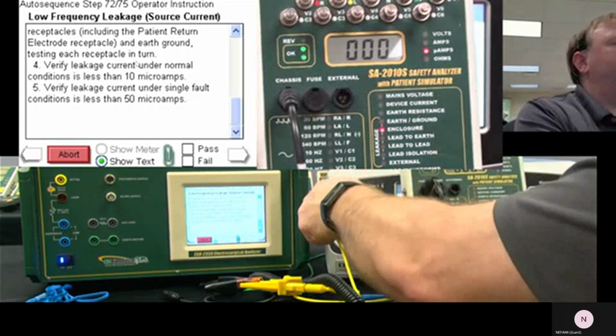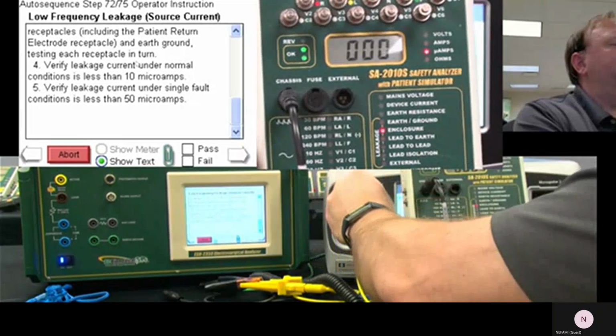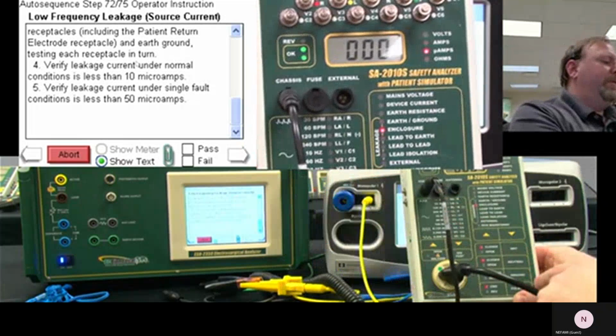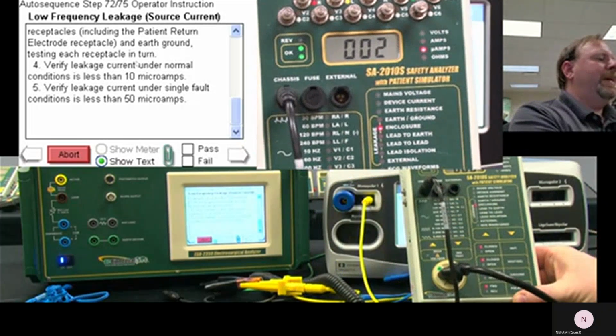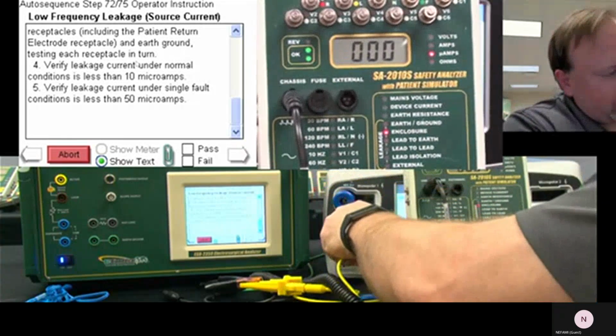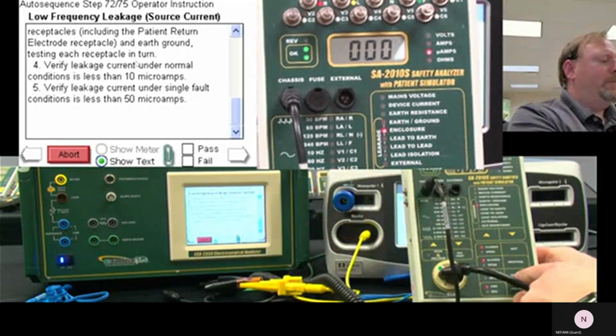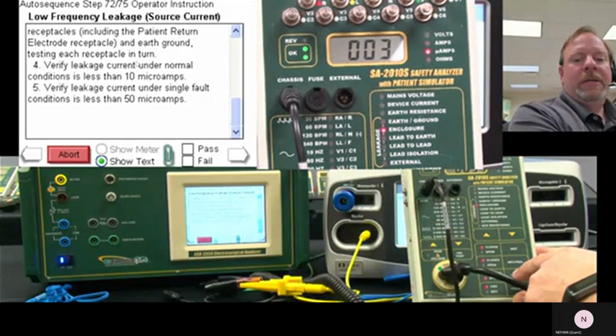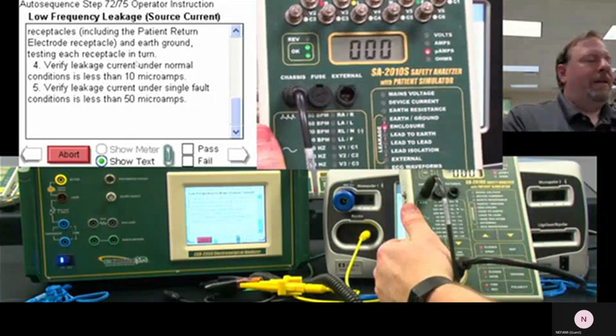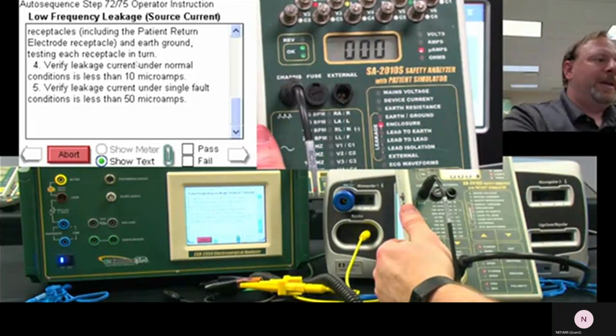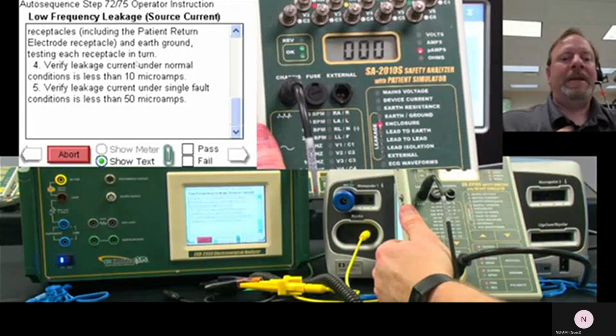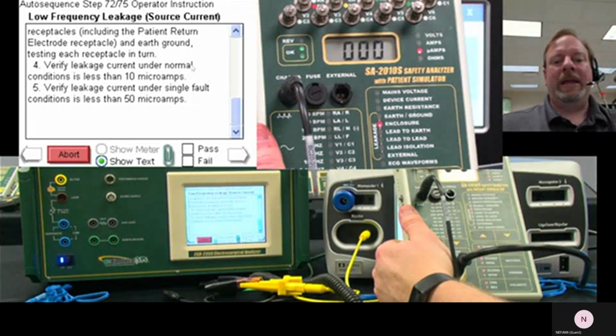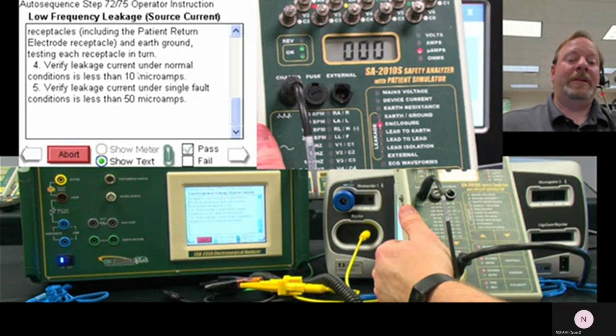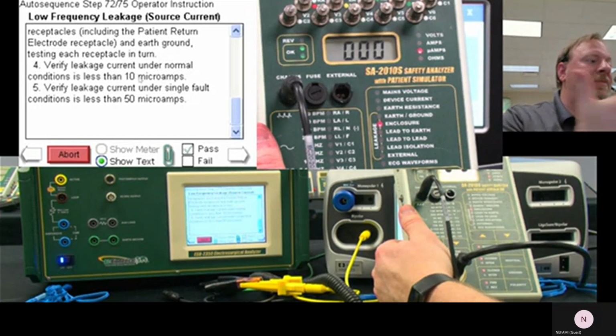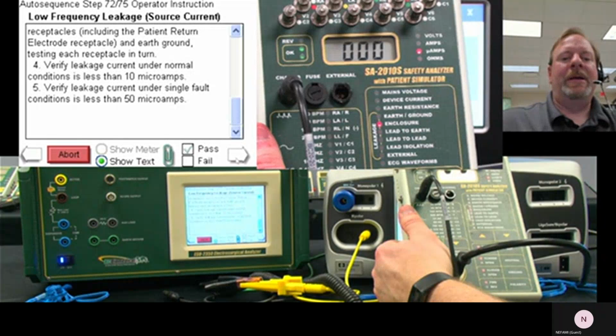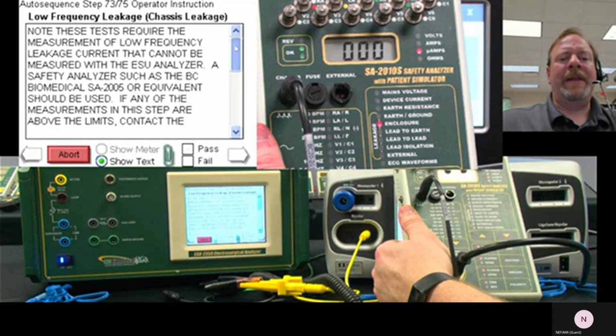So what we would do is go to each of these output ports on the FT10, look for single fault, look for regular. If anything is over that limit, then it fails. Again, the 2350 can't do this measurement, so it can't collect anything other than me saying, yes, I did this, and it either passed or failed. So I'm going to say it passed because the highest current we had was 2 microamps, well under the limit. And then I move on.